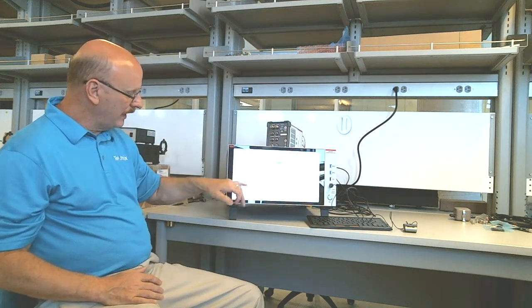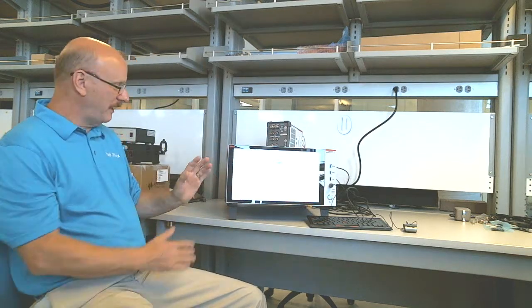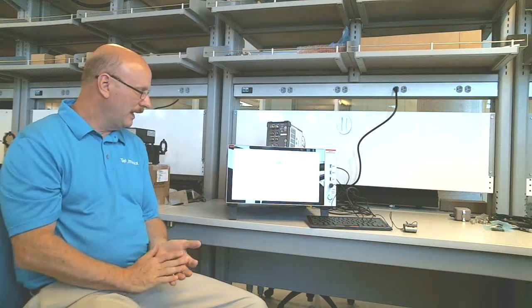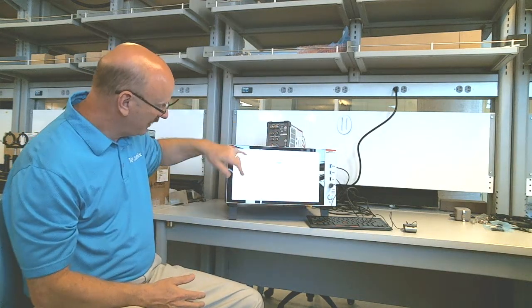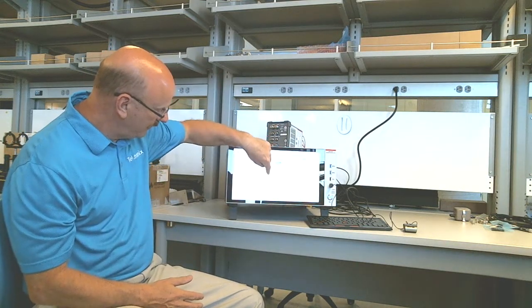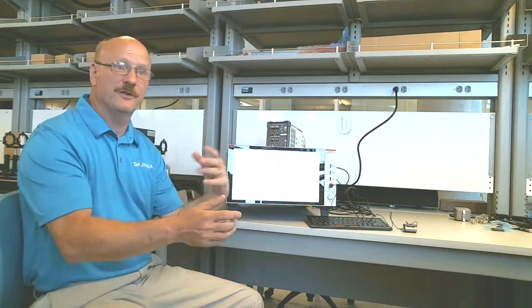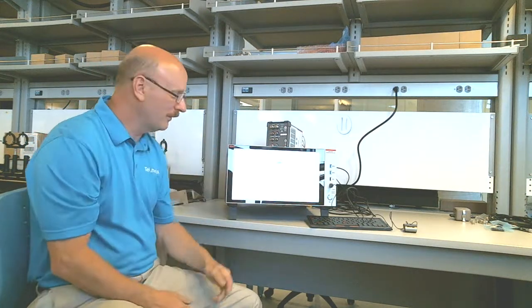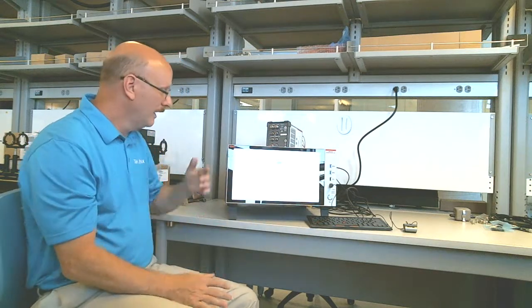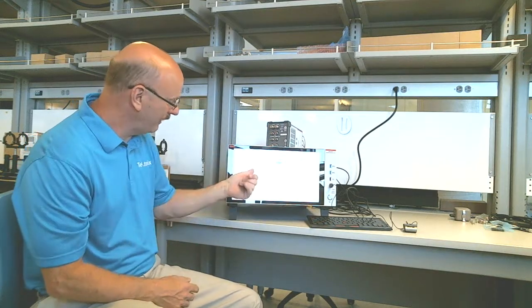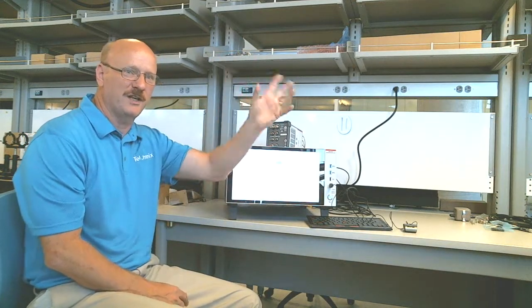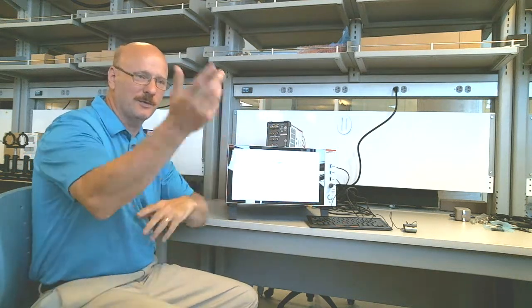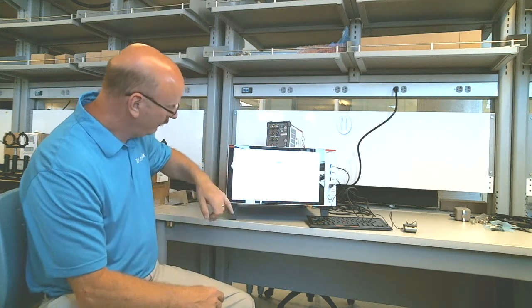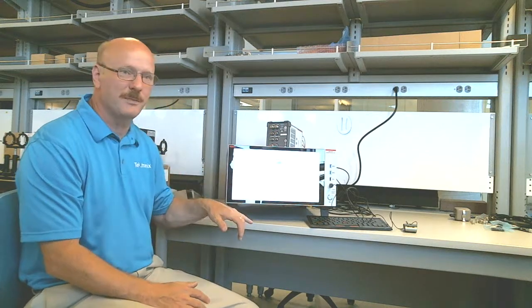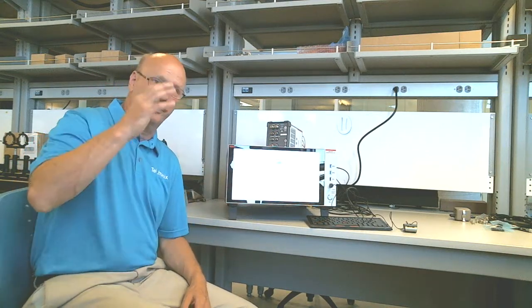You select what you want and hit add, and it throws it on the left side in this menu. For devices, if you want to test a particular type, they're all here, and you can use the right-hand side to filter by number of terminals, type of device, etc. Actions are things like beeping the beeper, showing a dialog box with a message for your operator, changing something, turning on a temperature controller, or whatever. You can put matrices in here too, so you can control switch matrices to test many devices in a production type environment.